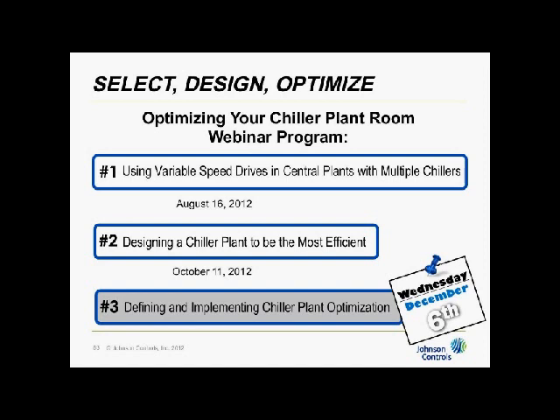Okay. Condenser pumps are variable or constant flow. In the primary-secondary system, the condenser pumps were run as constant flow, but we actually were putting VSDs on those pumps to eliminate balancing valves, but they were really running as constant flow. Over in the VPF system, the first VPF in the middle column there, we were running energy-based sequencing without doing anything to lower flow. We were keeping it constant. And the third column was when we lowered the flow down to the 80%. So all of the equipment in there had variable speed drives on it. It was really just a question of whether you ran them as variable speed drives. Variable speed drives can replace the functionality of a balancing valve and at least keep one of them open so that you don't waste head in the entire system forever through a balancing valve. And they're cheap enough now that it's worth it. Let's see what else.